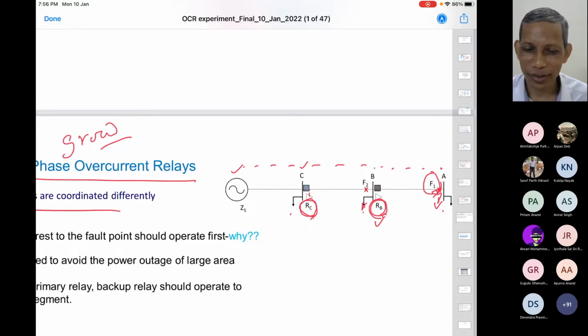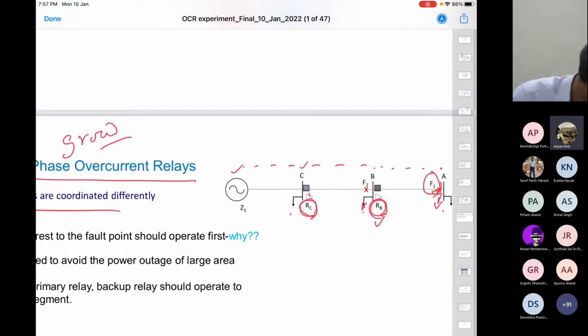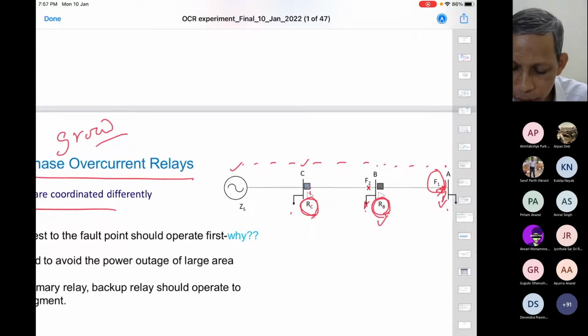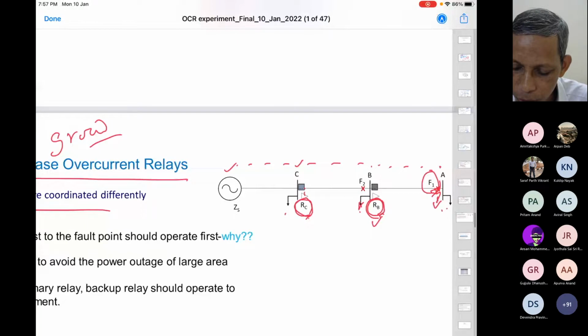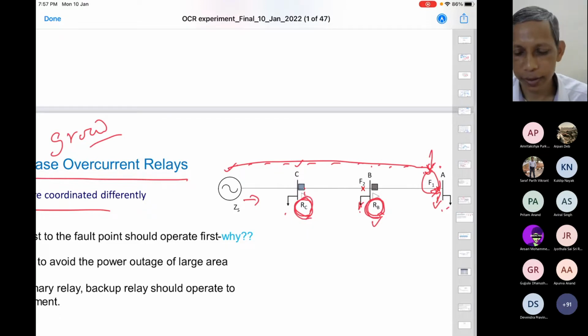Now let us say the situation happens to be something different. Sir, can you just explain this part again? See here, you understand that this is a 3-bus system. Load is connected here, here, and here. Otherwise, you don't require a bus, unless there is some utility. This is the source substation side. The fault happens to be at F1. I am discussing this fault only. For this fault, current will flow from this to this. So this relay will see current, and this relay will see the same current. I am calling it IF1.